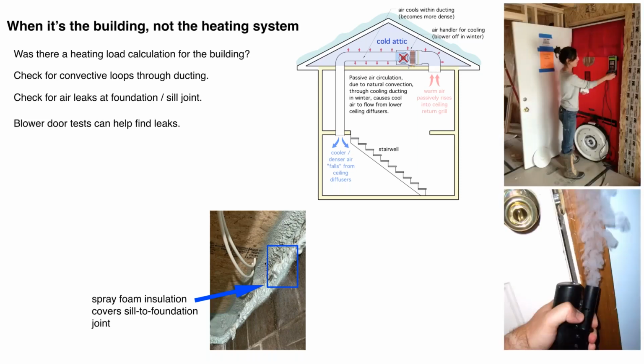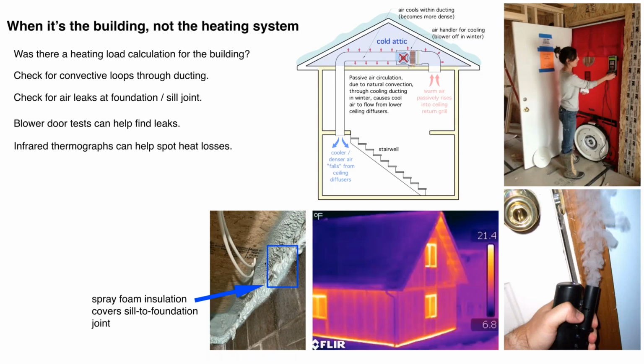A blower door test, certainly that's one way to help find air leakages in buildings, okay? With infrared thermography, you can find heat loss. You can also find areas where there's moisture trapped. So you've got tools available to do the building science, the diagnostics, and perhaps the load is quite a bit higher than what you anticipated or assumed when you did a heat load estimate for the building. Can you feel air coming in through the outside receptacles?